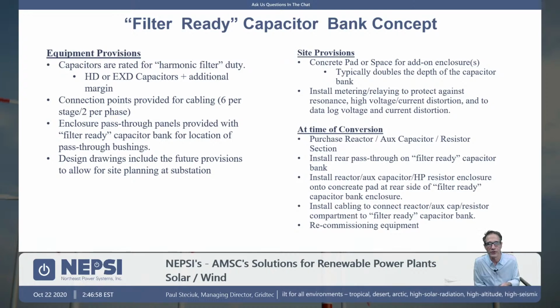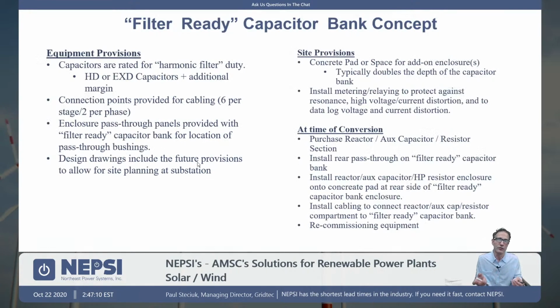So making sure that you specify that cap bank up front correctly is really important. And the filter-ready bank should include drawings for the future. All right, so if you have a filter-ready cap bank, make sure that the drawing package that you're approving in the end includes the provisions. How will it look when you convert this cap bank to a filter?